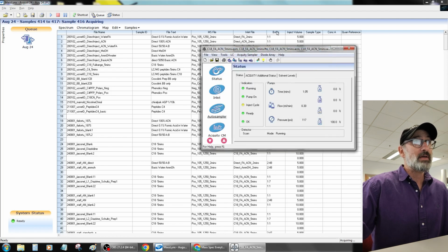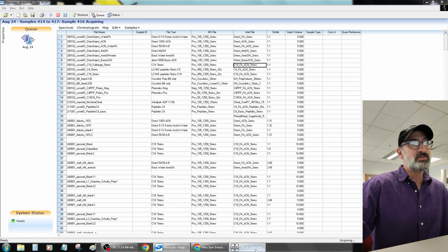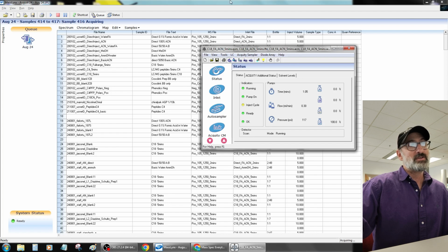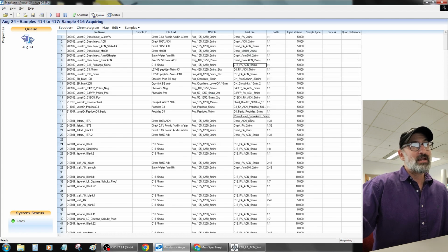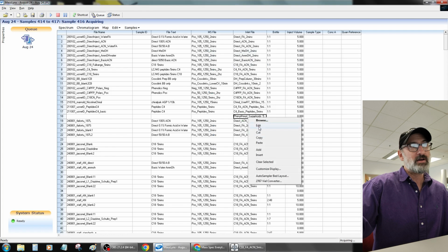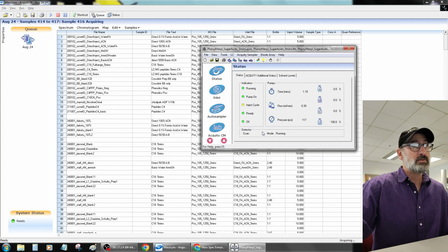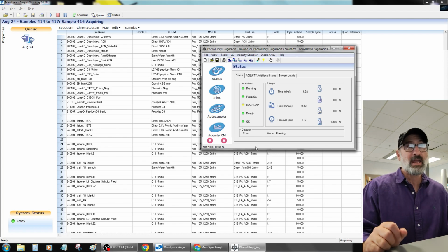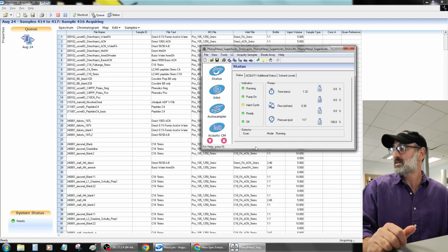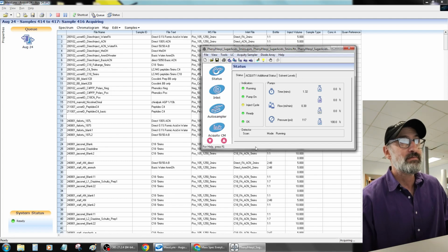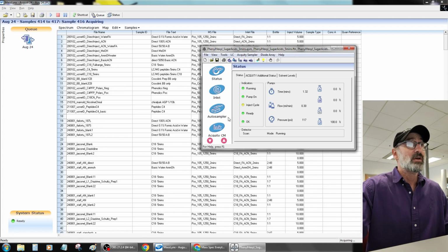All right, so one more method. Let's look at one more method. If you don't close the inlet file manager, that doesn't take as long to open. So then I'm going to look at a 5 minute method on what's called a phenyl hexyl column. So it's a hexyl with a phenyl ring at the end. It's good for pi-pi stacking, especially for sugars and acids and phenyl rings and things like that. I've even found it works pretty well for peptides, to tell you the truth.